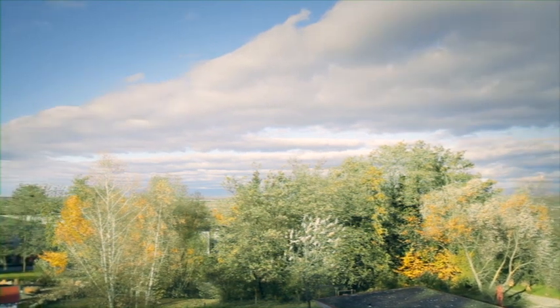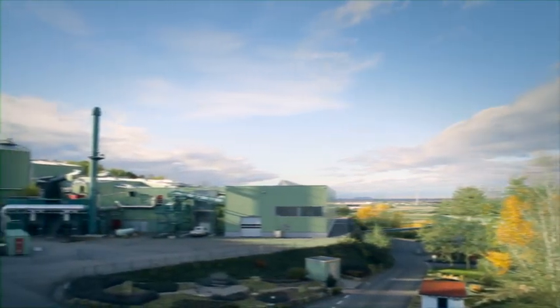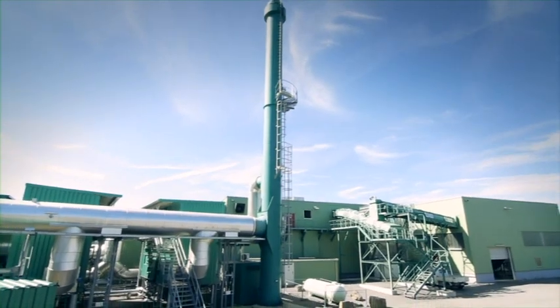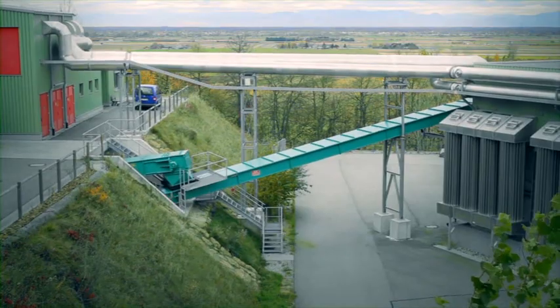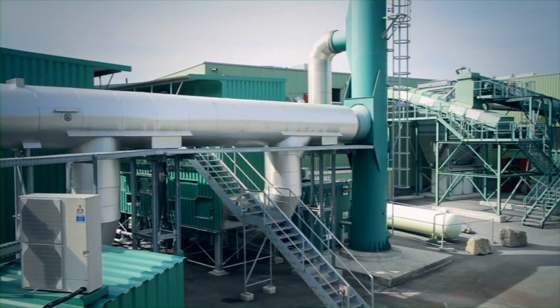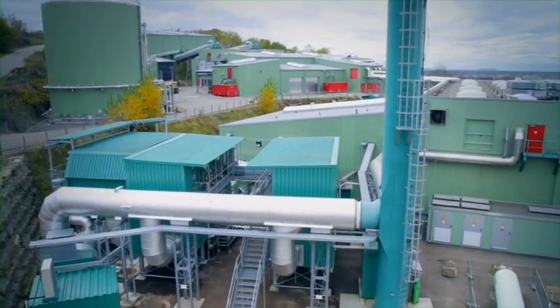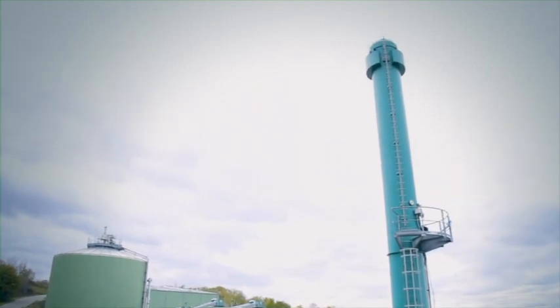In order not to spoil the natural environment with exhaust air, which is usually quite pungent, a differentiated and innovative exhaust air treatment system is in operation. All the process steps, systems, and conveying methods are enclosed, with the polluted air suctioned off on an ongoing basis and fed into the exhaust air treatment facility. Exhaust air which is less polluted, that from the halls for instance, is purified in biofilters.